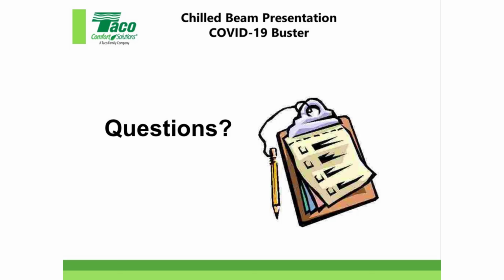Each one of those chilled beams I talked about, right? We had just the chilled panel, the passive and active. Each one of them, you only get so much cooling out of the first one, then you get a little more out of the second one, and then you get a lot more out of the third one when you look at BTUs.